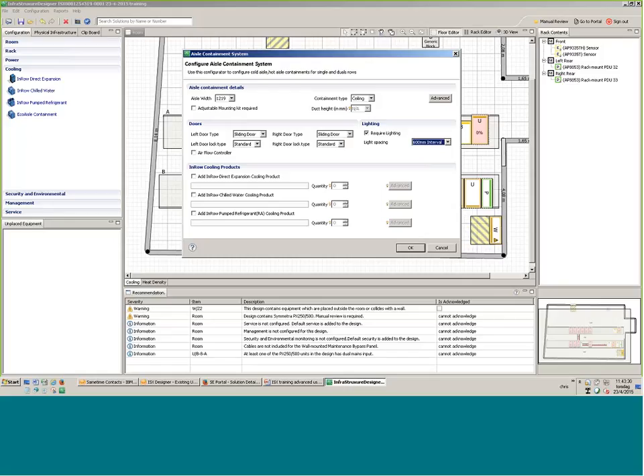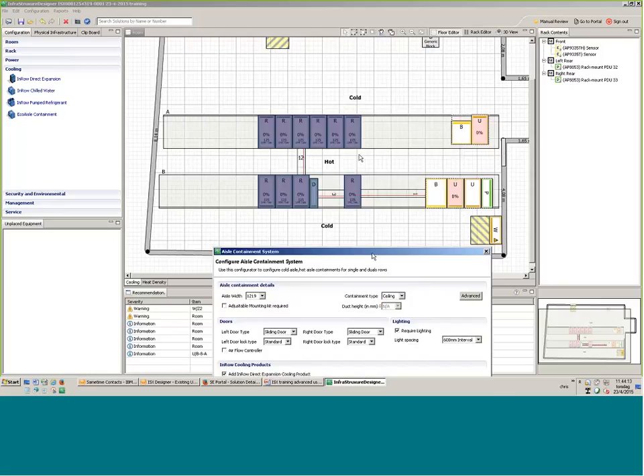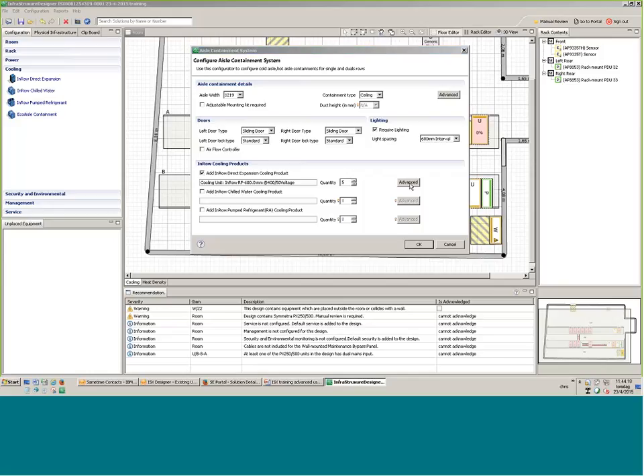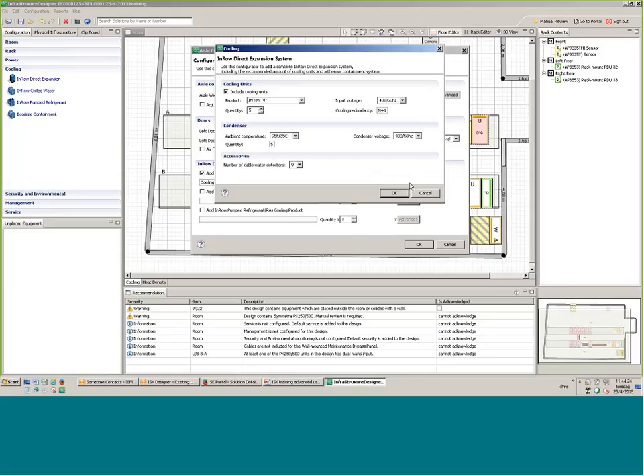So for the cooling units, you can select down here. We have the 3 options: direct expansion, which I will want to show, chill water, and the pump refrigerant. The pump refrigerant is, to say, quite a tricky system. So as soon as we see pump refrigerant, we will contact you to get more information. Especially water temperature or humidification in the room is quite tricky there. So if you select direct expansion cooling products, you have a recommendation here. This number is, as I say, a recommendation. It is not really true, so it's not perfectly calculated, especially in a room with different UPS all over. It will not work. So that's why we will take care of that and calculate it extra.